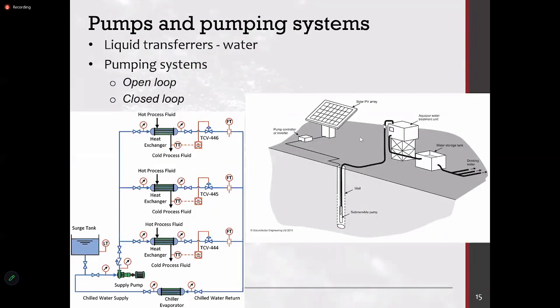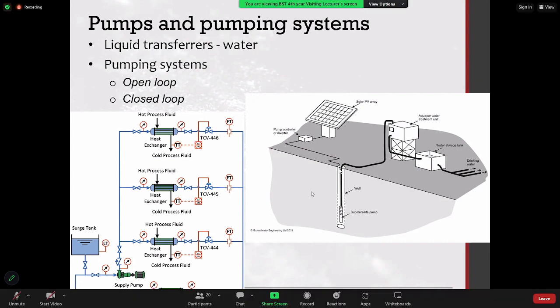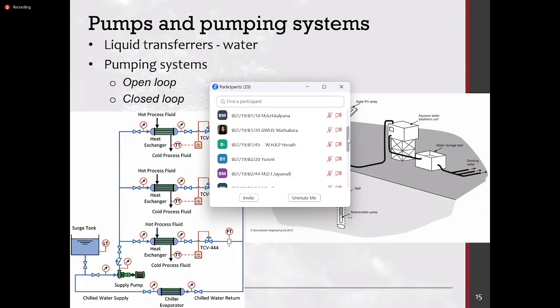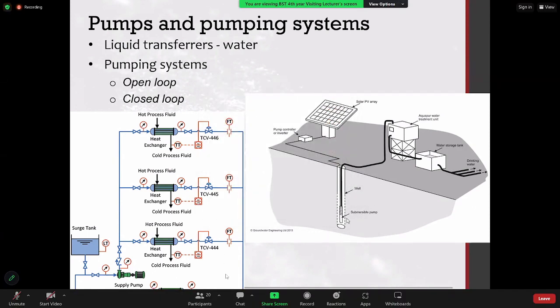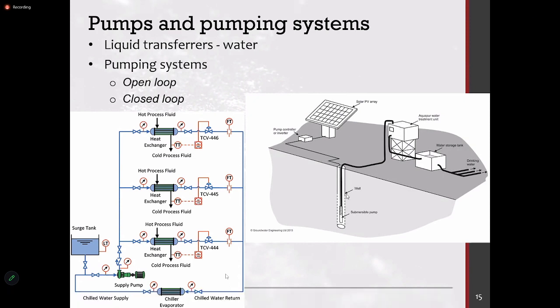So your head will be this difference: the height from the water level to the top of the tank plus your suction. We call these your suction head and your supply head. So if your pump is here, then you are providing the head difference, the height difference plus whatever friction losses you have in the piping system. Ideally, if you are piping from a submersible to the overhead tank, it has to be with minimum bends and minimum fittings to ensure the friction loss is minimized. But with distance, there is a certain friction loss which you can't avoid. Ideally, you take the shortest path and minimize the number of fittings.